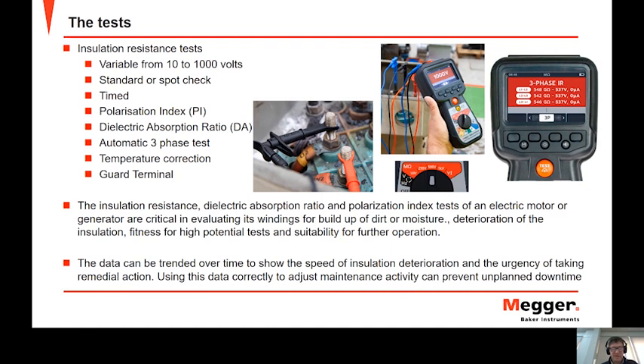Then within the IR test screen, we have the options of IR or spot check. We have a 3-phase mode, which allows us to make an automatic phase-to-phase IR test. So U to V for 1 minute, V to W for 1 minute, and W to U for 1 minute, fully automatically. And of course, to do this, we must be able to open the neutral point of the motor. Otherwise, we'll have a short circuit between the phases.